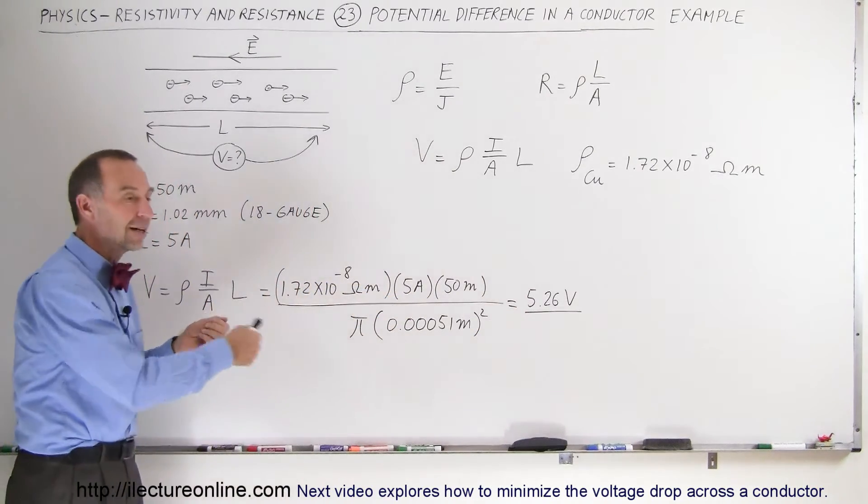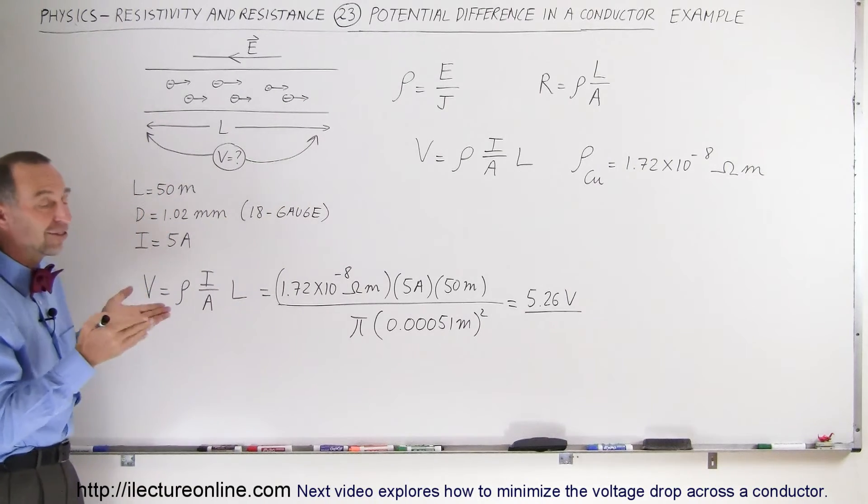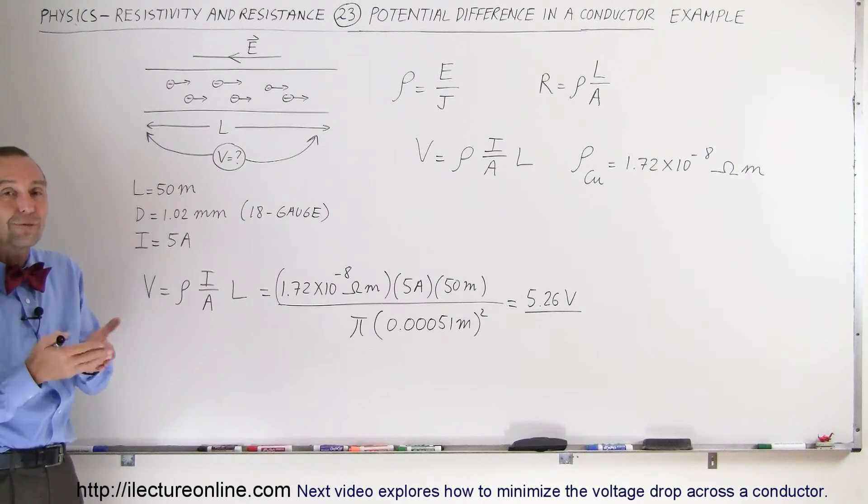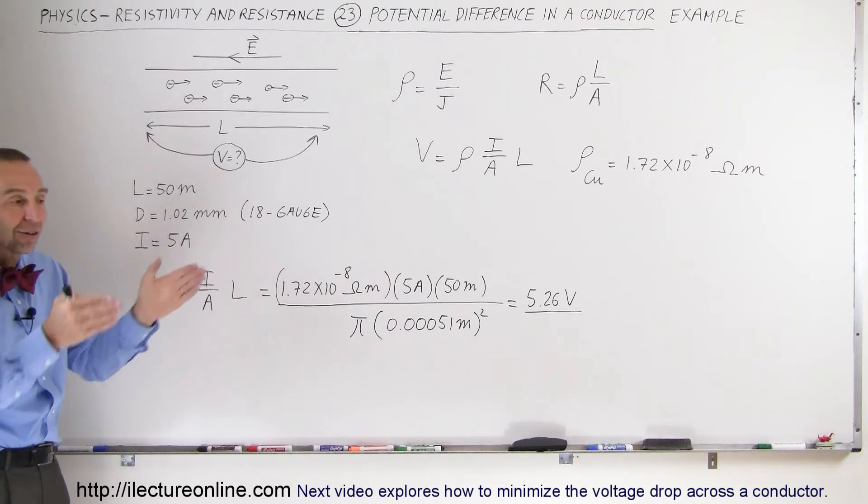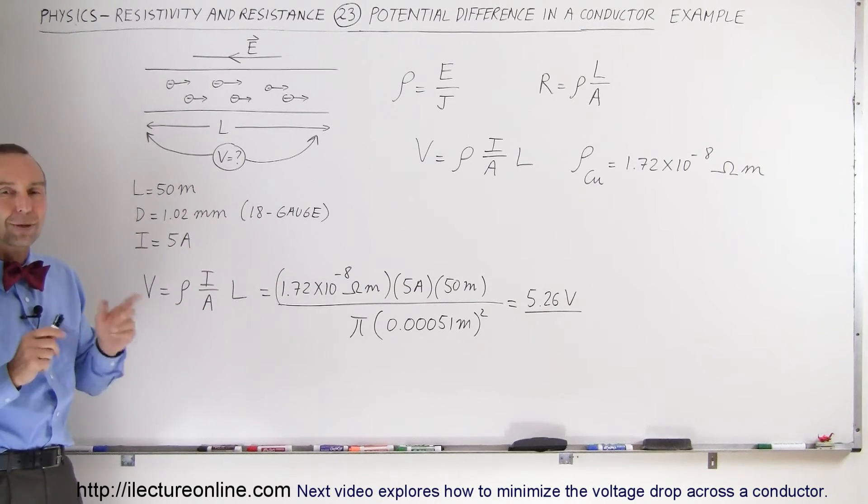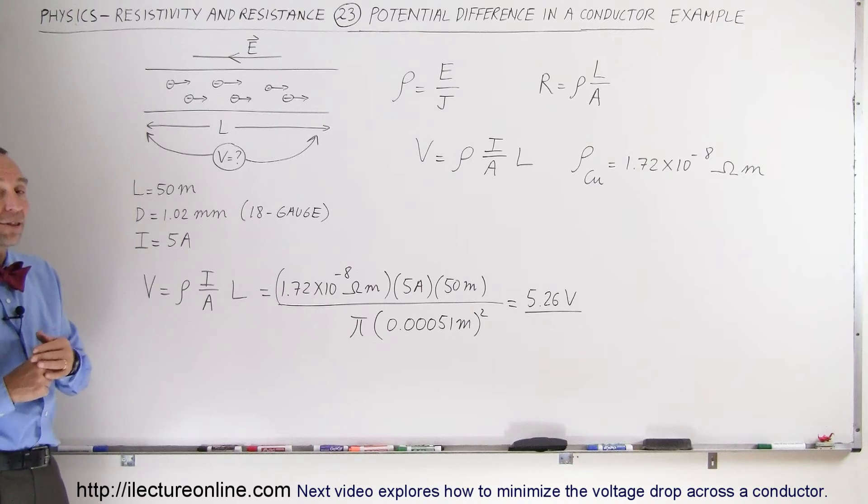So your output at the output socket is not necessarily the 117 or 120 volts you were expecting. It can be a little bit less because you lost some of the voltage drop across the wire. And 5 volts is not insignificant.